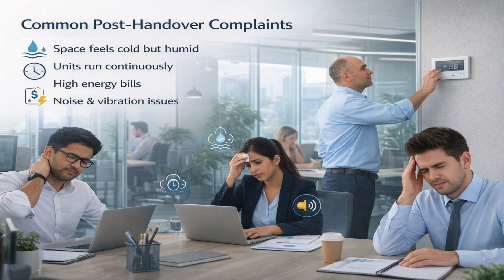In almost every project, there comes a moment, usually after handover, when the complaints start coming in. The space feels cold, but somehow it's still humid. The HVAC unit seems to be running all the time. Energy bills go up, occupants are uncomfortable, and very quickly, the HVAC system becomes the main point of concern. What's interesting is that when we go back and review the documents, everything looks correct. The units are approved, the calculations are submitted, the drawings are signed off. On paper, nothing is wrong.